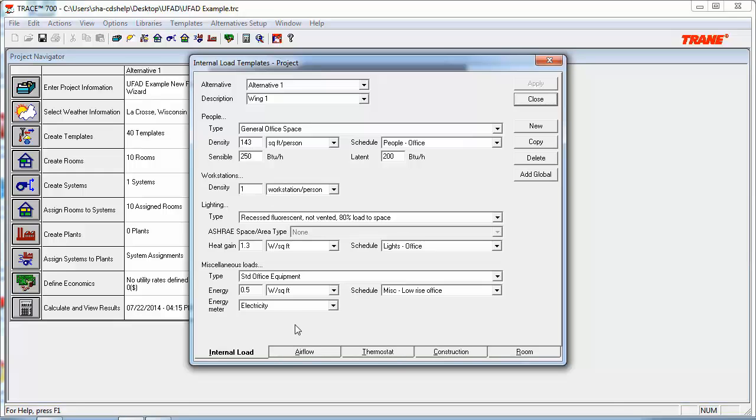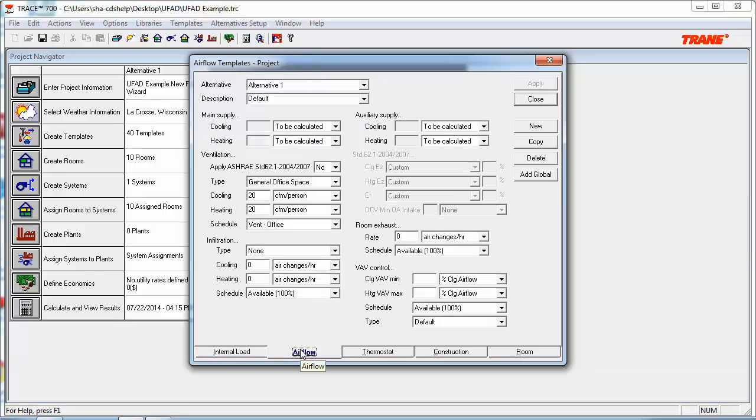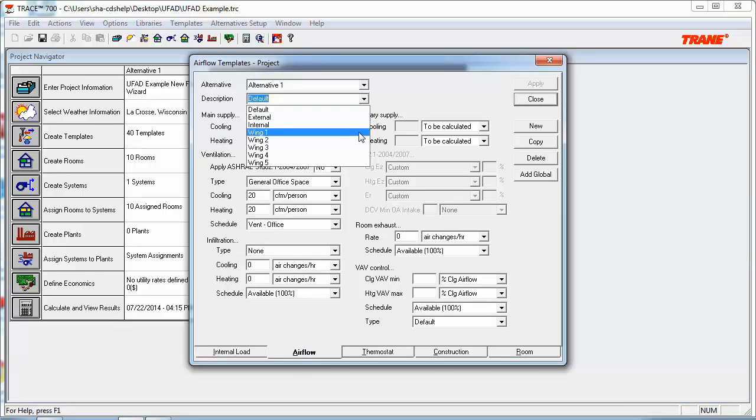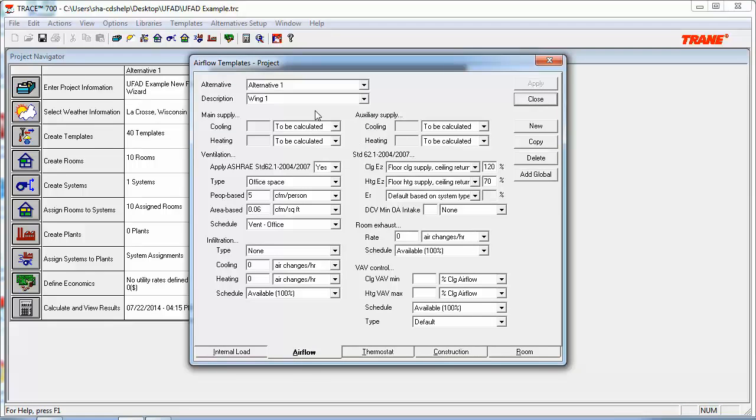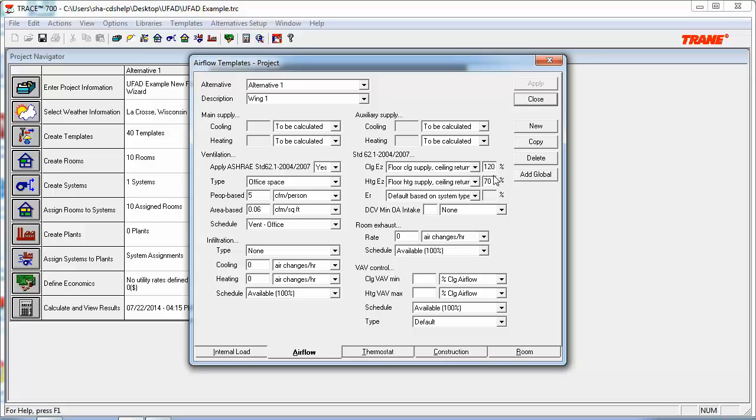Next, we can head into the Air Flows tab and take a look at the ventilation rates for this template. So, when we open up Wing 1, you can see that the ASHRAE 62.1 calculation is going to be applied for this specific room, and it has brought in the people and area-based inputs for the office space type. Prior to creating this video here, I've already done the Cooling Ez and Heating Ez inputs as appropriate for a UFAD system type. So, for Cooling, we have 120% effectiveness, and Heating, we have 70% effectiveness.